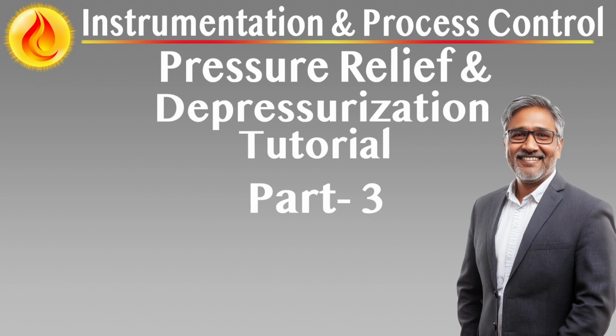If rapid repressurization is possible, consider the combined effects of high pressure and low temperature when selecting materials. Material selection must comply with relevant fracture toughness criteria and applicable piping and pressure vessel design standards.